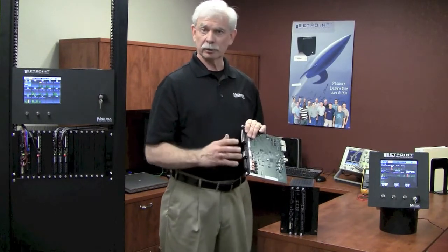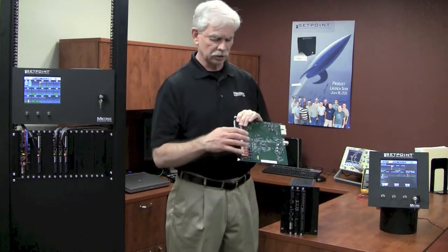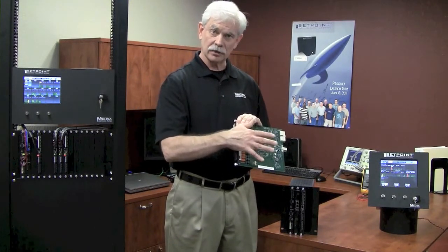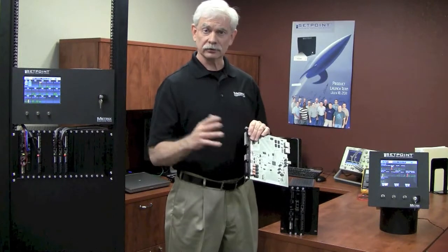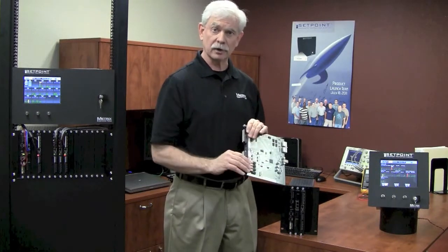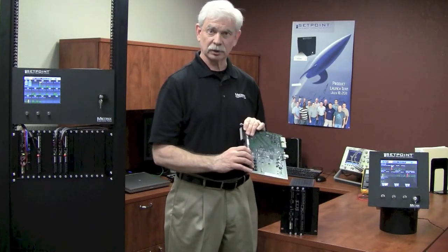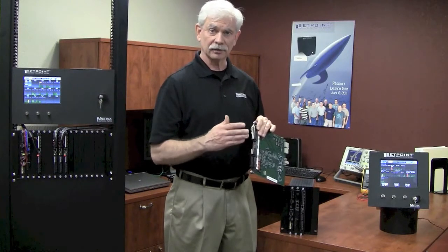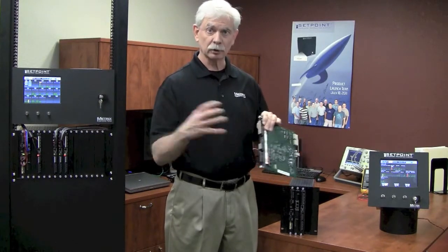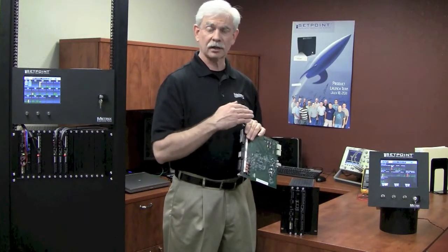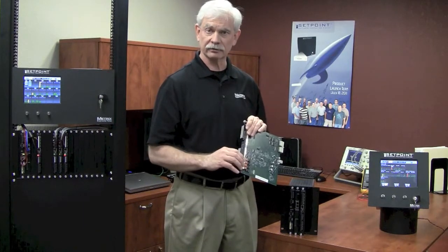Now it's probably important to note that these relays can be used for the signals that are on the card, or they can be used for signals that are from elsewhere in the rack. Those relays are very flexible, and they can be programmed for not only other channels but groupings of channels with logical AND voting and OR voting and other types of voting.